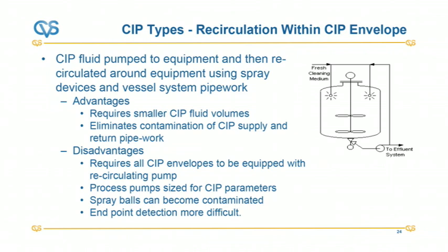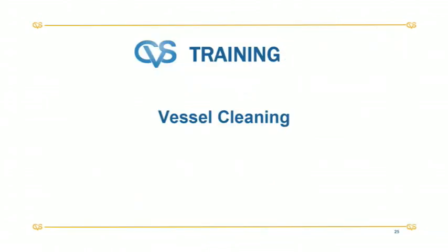Advantages are smaller CIP volumes, and it eliminates contamination of the CIP supply. But the disadvantage is it requires all the CIP envelopes to be equipped with a recirculating pump. Process pumps have to be sized for the CIP parameters, and spray balls can be contaminated. In some cases, endpoint detection with this, especially if we're looking at conductivity and things, can be a little bit more difficult. But you can protect spray balls with filters or strainers in that system. Certainly if you've got static spray balls in there, you'd want to do that anyway.